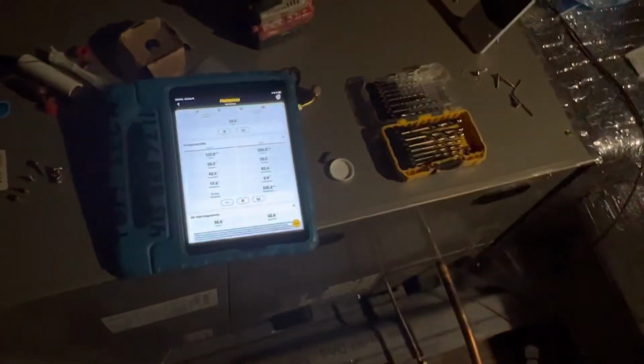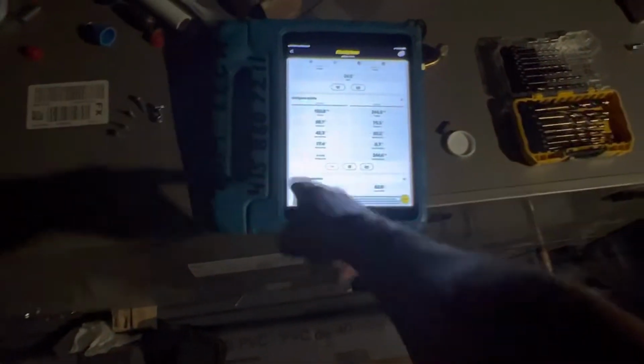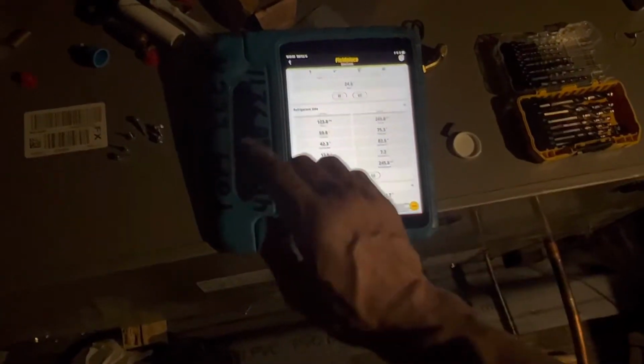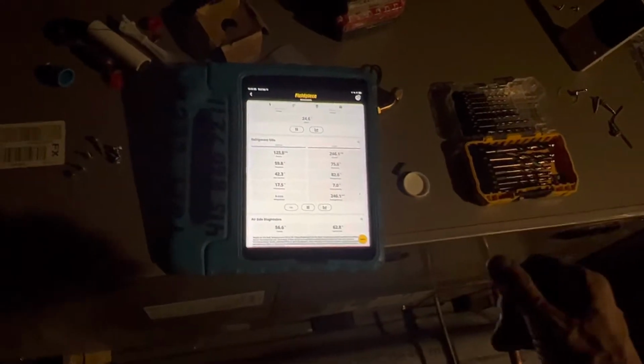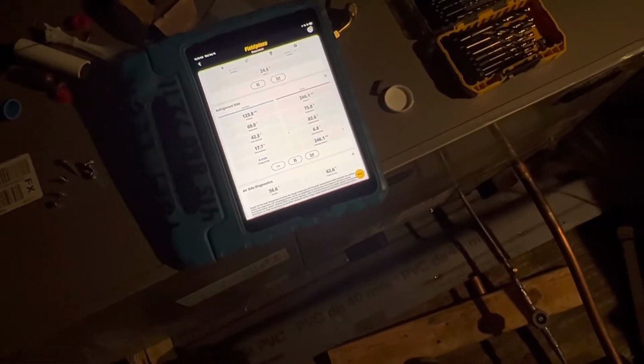And the other thing I'll have to come back for is the airflow, because we know it's a little wonky. I have to actually use my TrueFlow grid and measure and test the airflow inside this thing, because if the airflow is incorrect, all my numbers are incorrect. I could be adjusting and I could get good looking numbers, but they'll be incorrect because the airflow is not correct. But I will get it operating good right now, and that'll give your guy time to insulate.